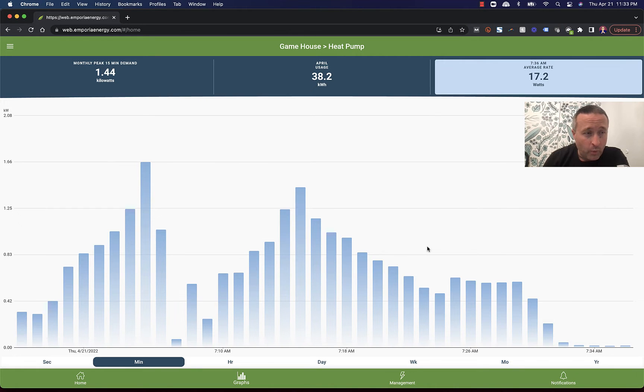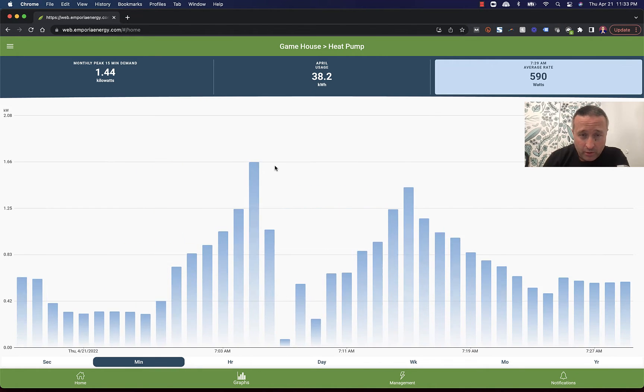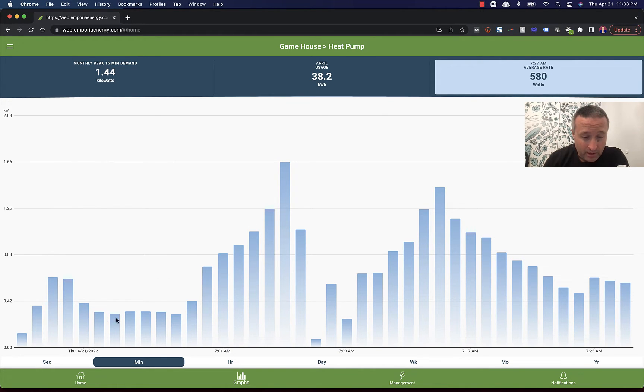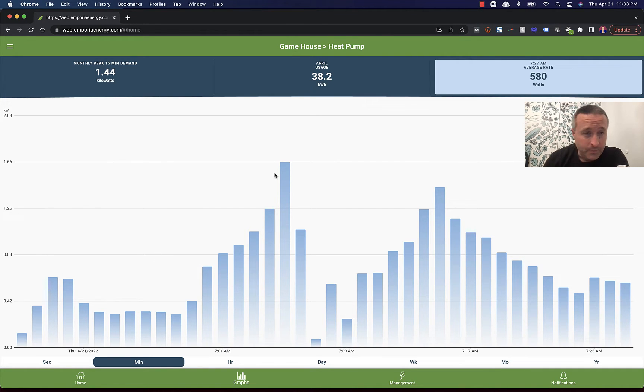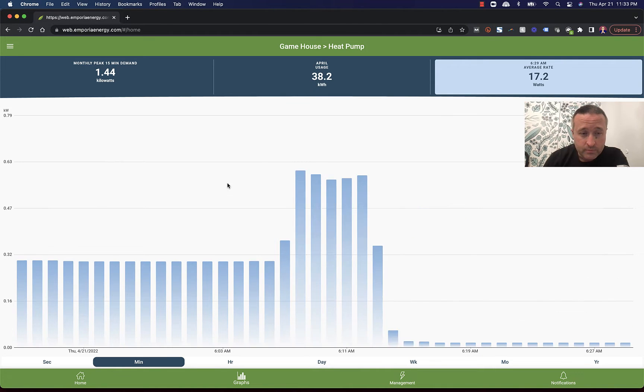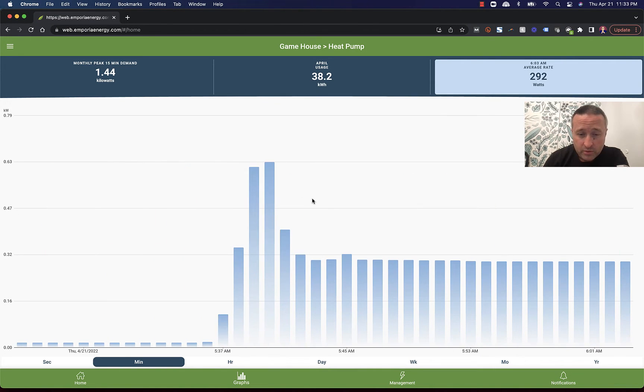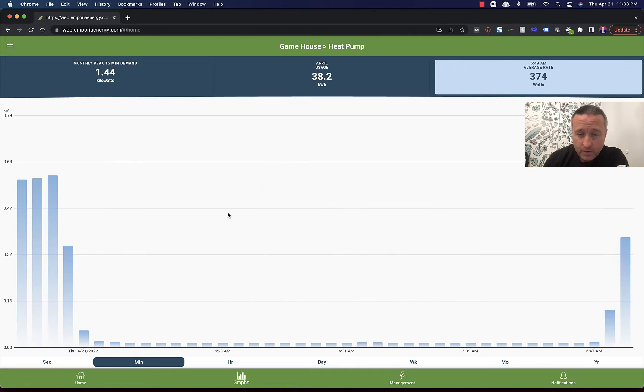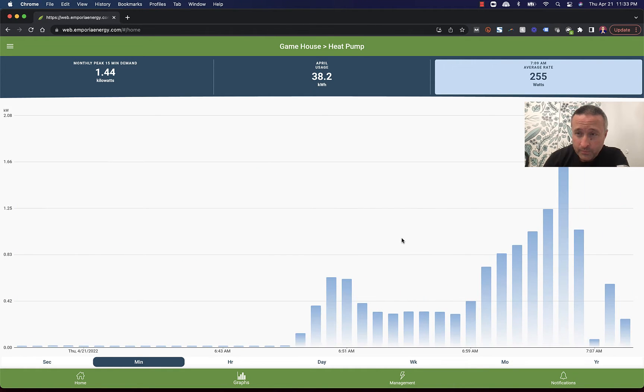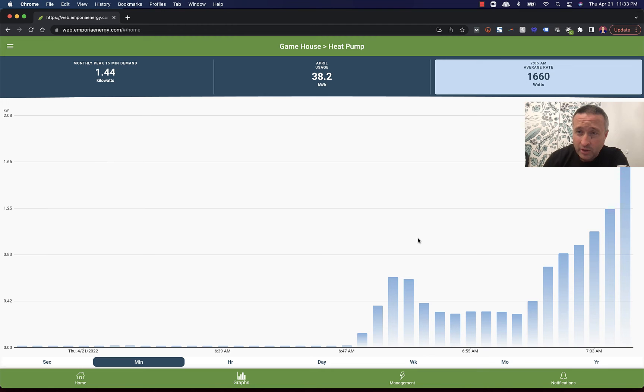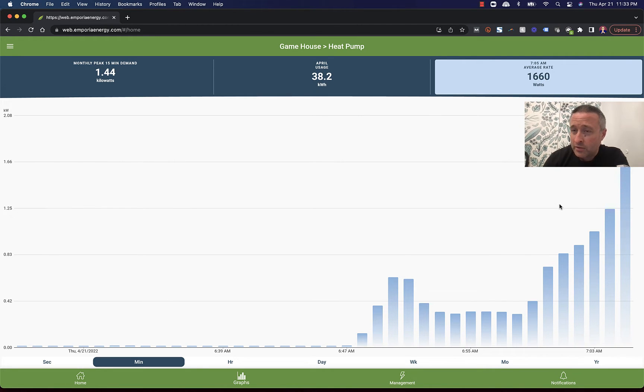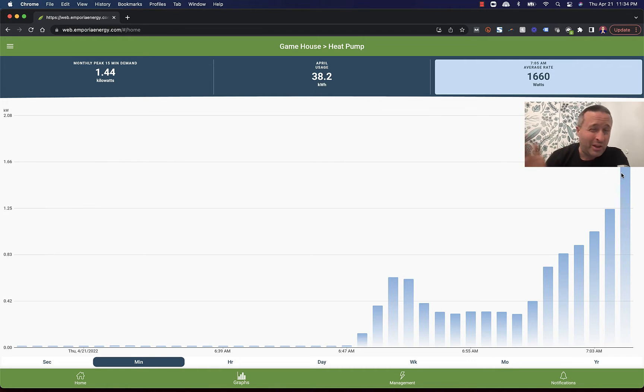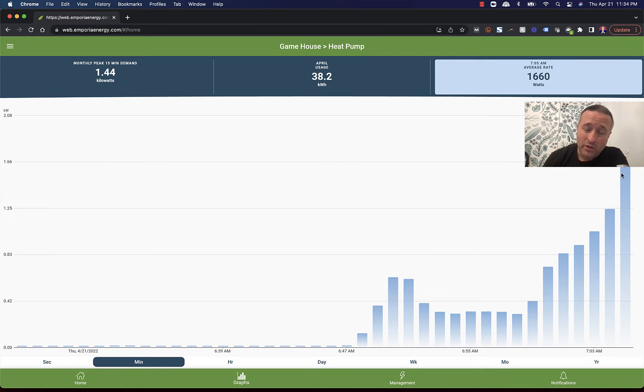So it's pulling about 600 watts here at the end before it starts shutting down. But one thing I found was interesting, note how tall this bar is. So it was already running when I turned the heat up. I turned the heat up right around 7 o'clock. And you can see it ramped up. Let's see just how high that went. It went too far that way. 1660 watts. So that was average for that minute. That is flat out more or less. I've seen 1750 watts, something like that. This is a one and a half ton unit. It's pretty close to a thousand watts per ton in my experience.